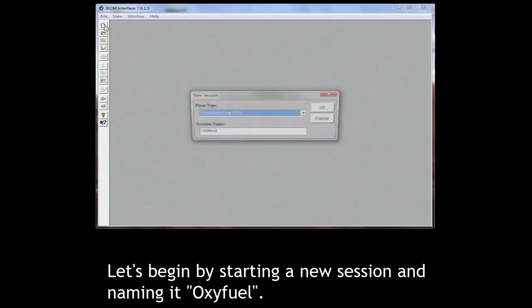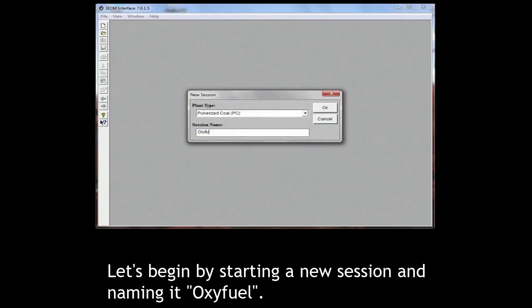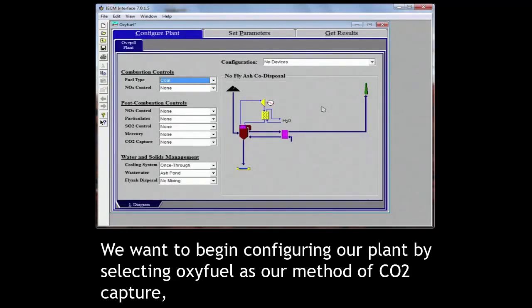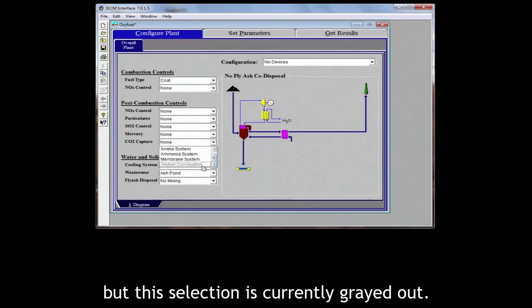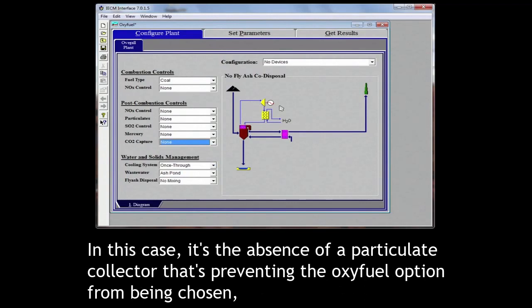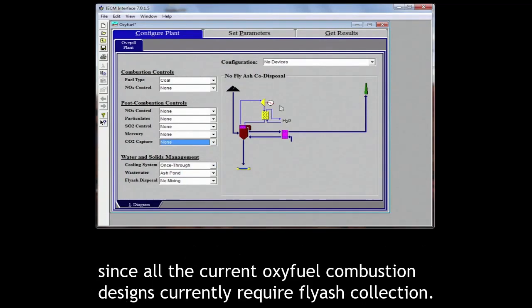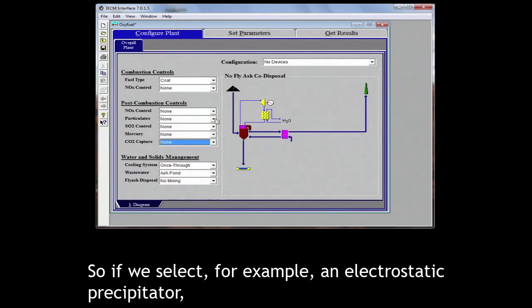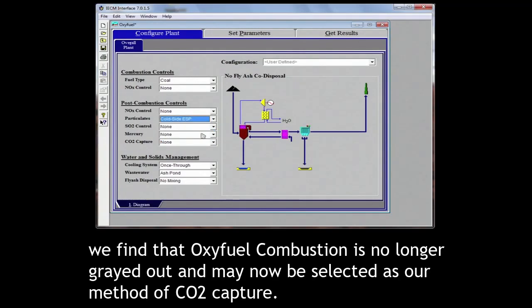Let's begin by starting a new session and naming it oxyfuel. We want to begin configuring our plant by selecting oxyfuel as our method of CO2 capture, but this selection is currently grayed out. This means that there are some other design choices which must be made in order to have this option available. In this case, it's the absence of a particulate collector that's preventing the oxyfuel option from being chosen, since all current oxyfuel combustion designs require fly ash collection. So if we select, for example, an electrostatic precipitator, we find that oxyfuel combustion is no longer grayed out and may now be selected as our method of CO2 capture.